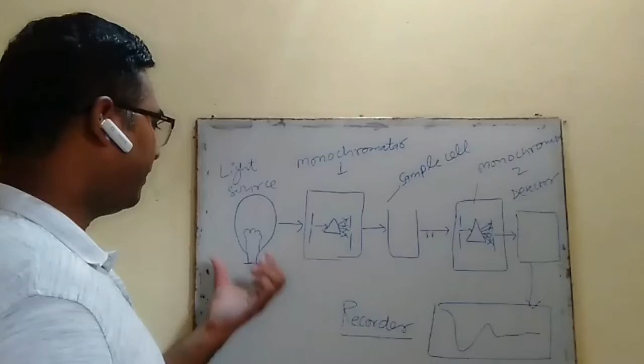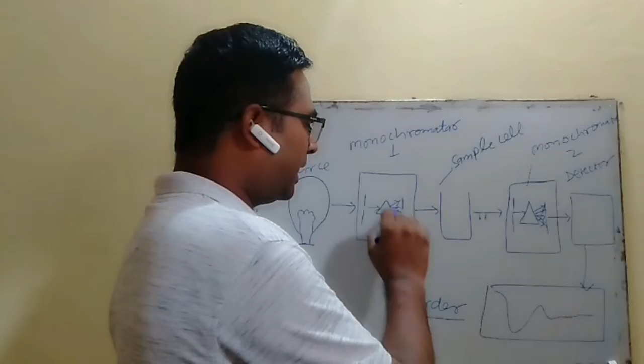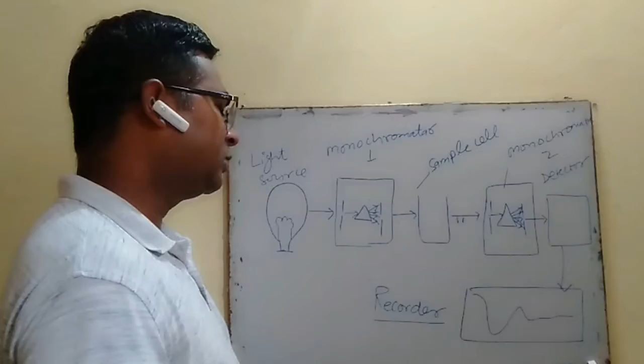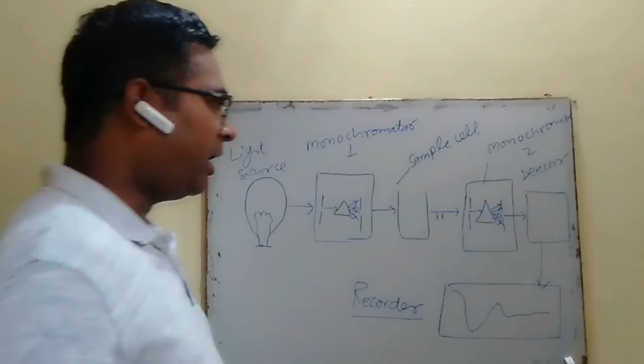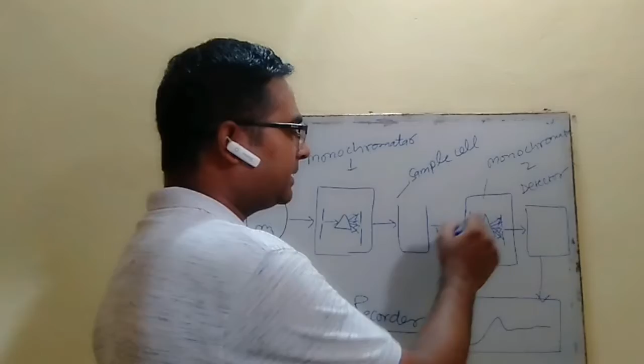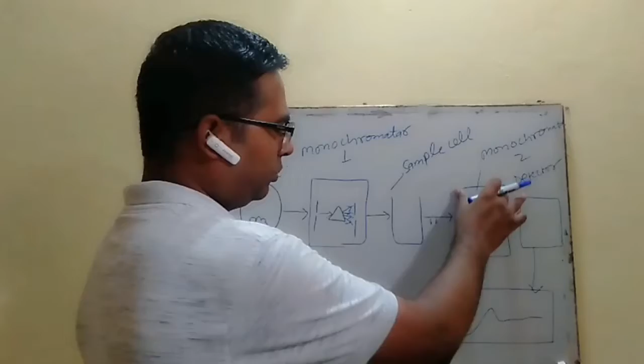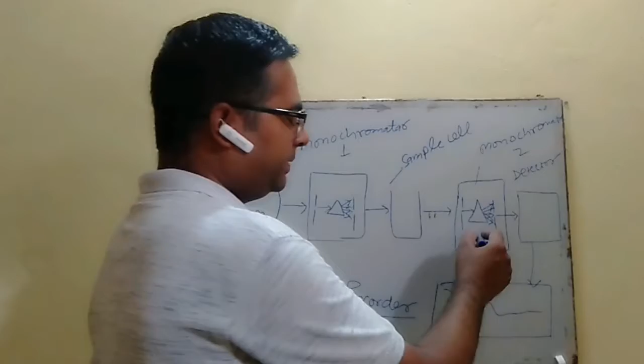So the energy in the form of radiation emitted by the source passes through monochromator 1, which isolates the desired wavelength of light that passes through the sample cell which contains the sample. The molecules present in the sample absorb the radiation, and the rest of the emitted light passes through monochromator 2, which isolates the desired wavelength of light which passes to the detector. Generally a photomultiplier tube is used in a spectrofluorimeter, and the signal is sent to the recorder, which records a spectra.